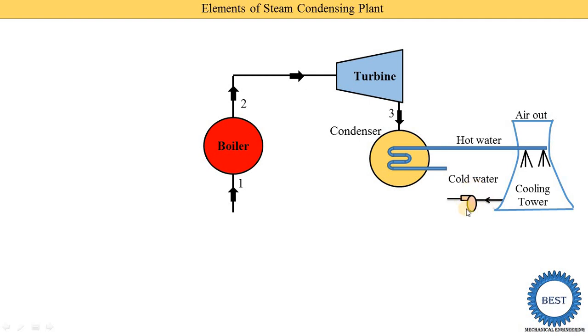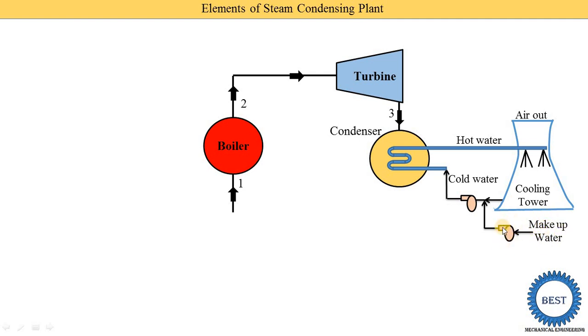The next component is the cooling water pump. This cooling water pump supplies the cold water to the condenser. During the cooling of the water in the cooling towers, some quantity of the water is evaporated. So we need to add the make-up water — that is, we need to add fresh water. Here we supply this make-up water using the make-up water pump.